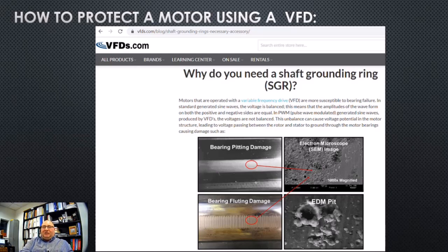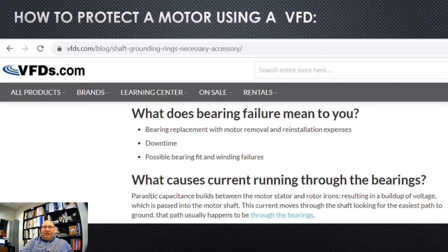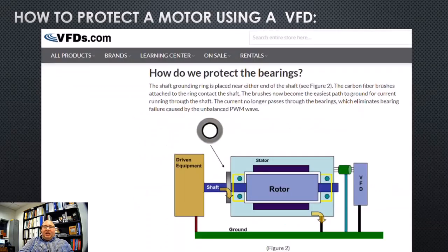The imbalance could cause a voltage potential in the motor structure, leading to the voltage passing between the rotor and the stator to ground through the motor bearings, causing damage. And some of the damage would be a bearing pitting, SEM image of that particular pitting, bearing flute damage, and EDM pitting. So the solution then is to add some products here, right? And VFDs.com does sell it, all right? And it's called a shaft grounding ring, or it's sometimes known as a shaft grounding strap, right?